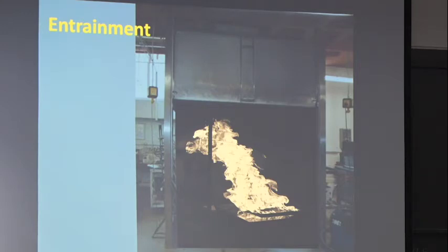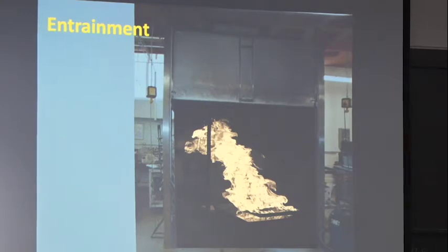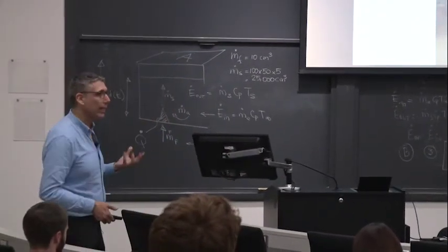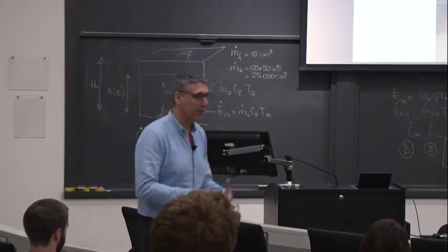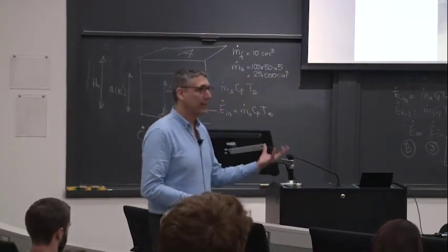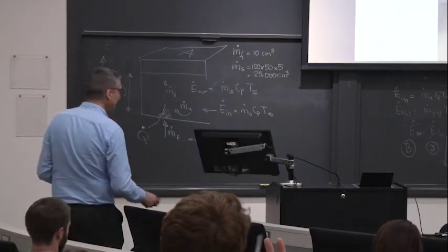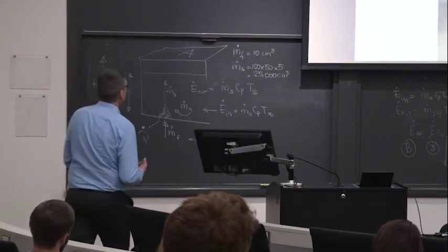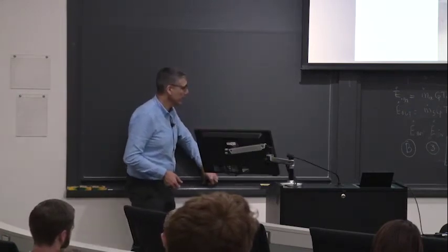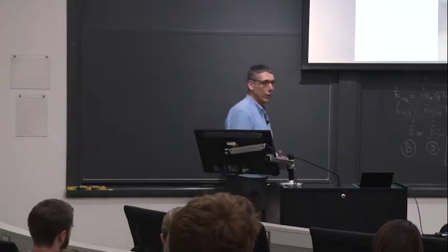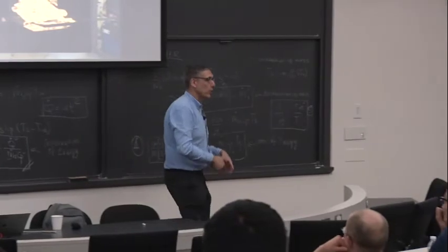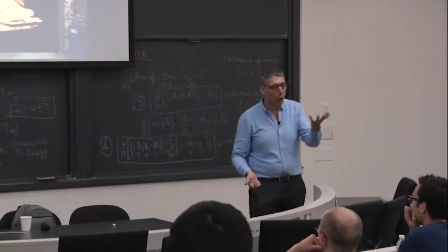the person who devised this was an individual called Gunnar Heskestad. You know, he used to work at FM Global. And basically, they couldn't figure out a way to estimate appropriately how much air would be entrained in the event of a fire. So they decided to perform an experiment. And I would like you to tell me, how would you run an experiment to determine the amount of air entrained? I'm giving you plenty of hints in there, and of course you have the notes in there, so you in principle should be able to tell me, but the logic is what is important.